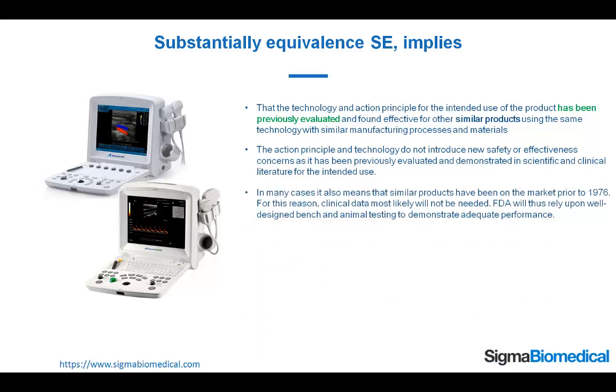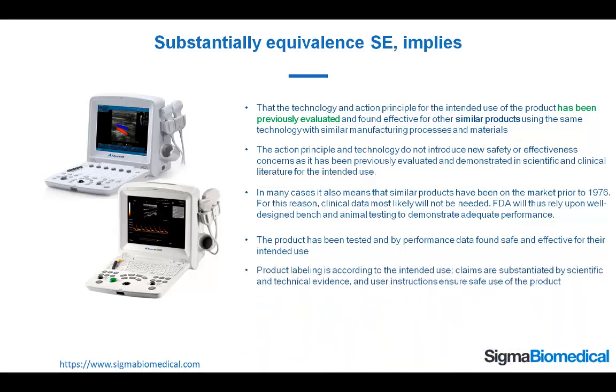In many cases, it also means that similar products have been on the market prior to 1976. For this reason, clinical data most likely will not be needed, and the FDA will rely upon well-designed bench and animal testing to demonstrate adequate performance. The product has been tested and by performance data found safe and effective for their intended use. Product labeling is according to the intended use, claims are substantiated by scientific and technical evidence, and user instructions ensure safe use of the product.